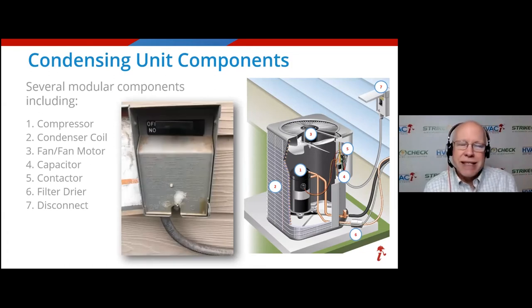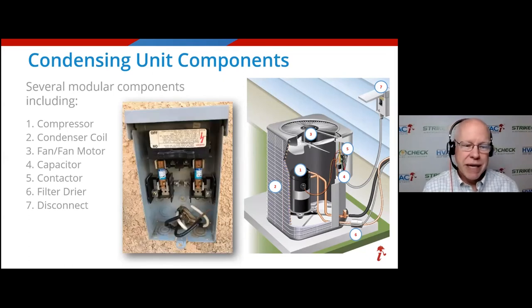Could also be a simple, or what I would call a low-tech, disconnect. You might have a pull tab at the top. You have two copper plates in there that break the electrical current. What a lot of people don't know is these also could be part of the loss because many of them have fuses in them. Again, designed to protect the system in a surge event. Change out those fuses if they're blown, system fires right back up. Easy repair for a technician, probably under deductible.